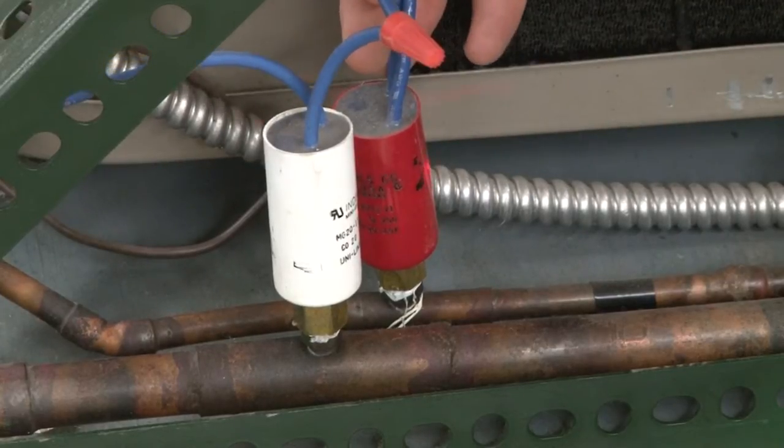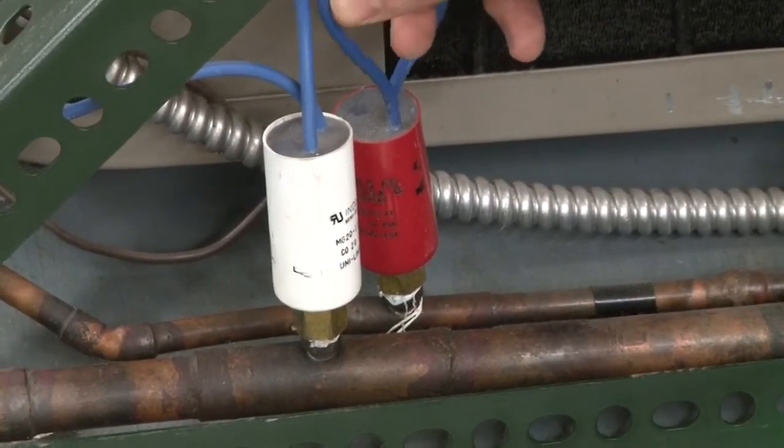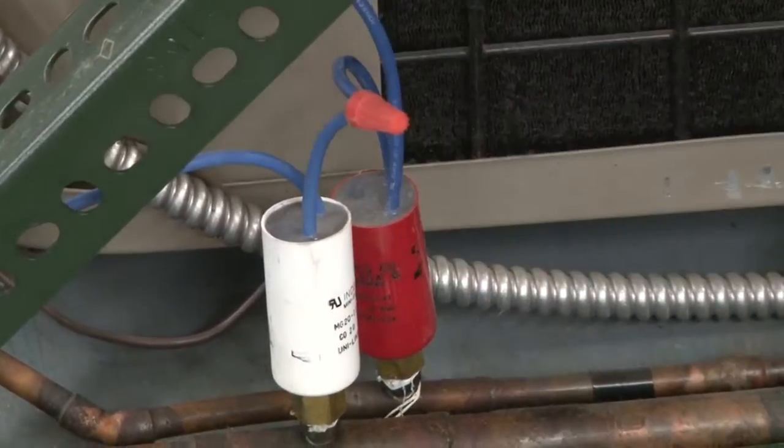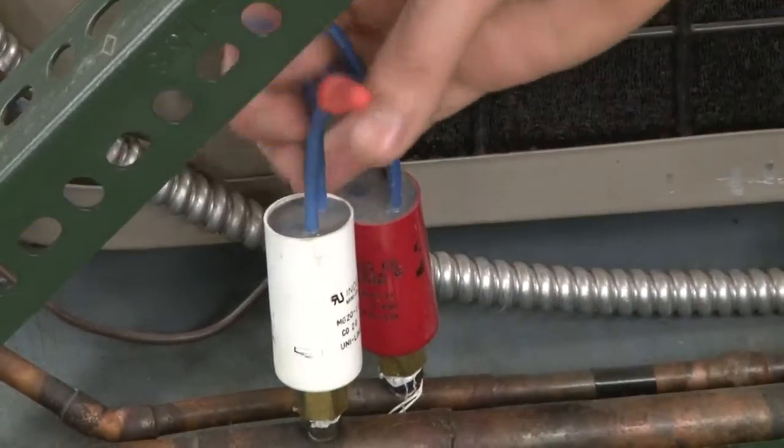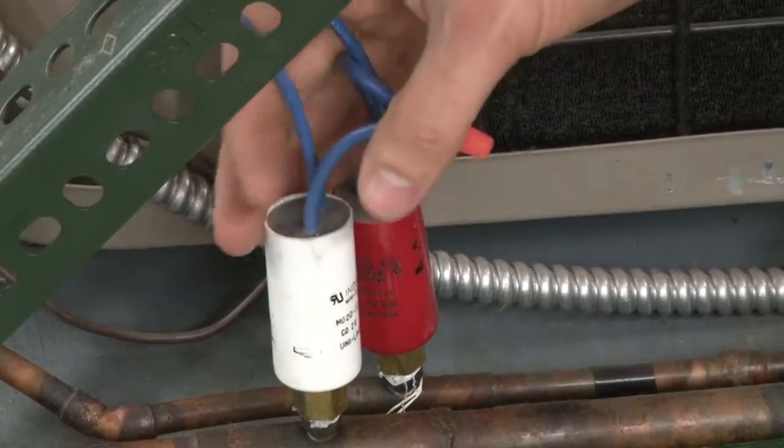Your high side pressure line, if our pressure gets too high, this would open up and shut off our system through our contactor. Again, they're wired in series together through our contactor.